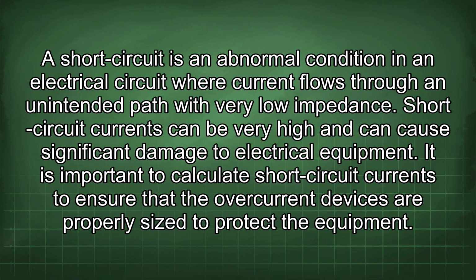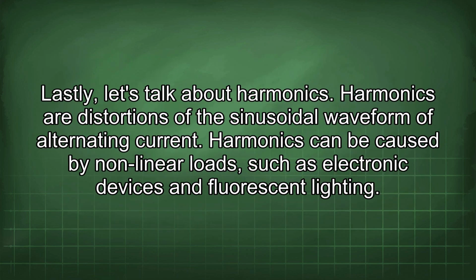And then let's briefly cover short-circuit current calculations. A short circuit is an abnormal condition in an electrical circuit where current flows through an unintended path with very low impedance. Short circuit currents can be very high and can cause significant damage to electrical equipment. It is important to calculate short circuit currents to ensure that the overcurrent devices are properly sized to protect the equipment. Lastly, let's talk about harmonics.